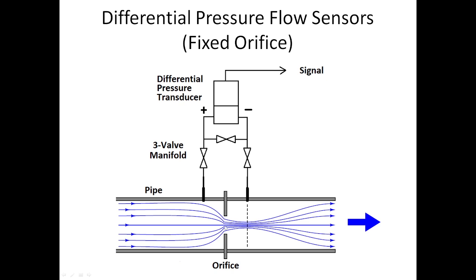Now this type of flow sensor is perfectly fine if you have a very specific flow rate that you're going to work with. Unfortunately, with medical applications, you're going to have pediatric patients, you're going to have geriatric, obese patients, large patients, small patients, male and female, old, young. They're all going to take different ventilation settings, which means they're going to have a different pressure and a different flow rate. So a fixed orifice is good for some applications, but for many patient applications, you're going to see that they're going to have something called a variable orifice.